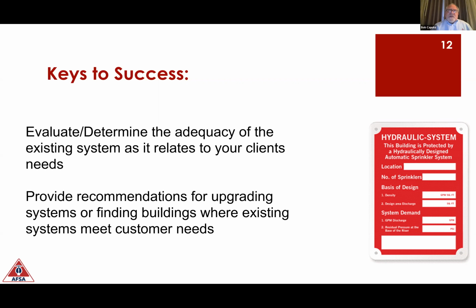So let's say we had a fire sprinkler system that's designed for a 3,000 square foot area. If the building is 80,000 square foot big, the fire sprinkler system only has enough water and pressure to deliver the water needed to a 3,000 square foot area of that building. And by the way, in warehouses, a fire sprinkler system can only cover 40,000 square foot of floor area. So if you have an 80,000 square foot building, you're going to have at least 2 fire sprinkler systems in that building. The reason for that is when we take a system out of service, we don't want to take the entirety of a large building out of service.